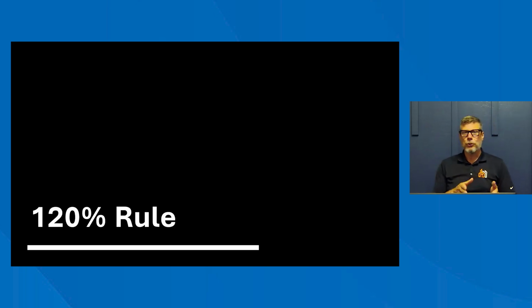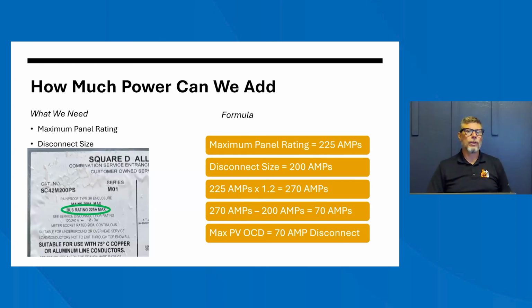So let's talk about the 120% rule. This one can be confusing to anybody, but it's a pretty simple formula. This is how we're going to determine how much power can go from the grid and from your array into your panel. When setting up the PV system, the amount of power that can be added to your service panel is actually determined by the 120% rule. This is an NEC thing. This ensures that the combined amperage of the main service breaker and your PV breaker do not exceed 120% of the panel's bus bar rating.